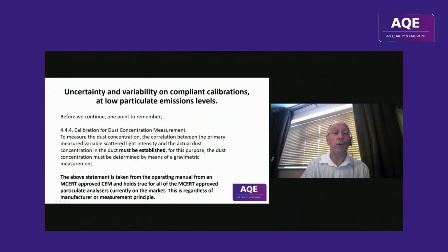Again, it's just confirming the point that no continuous emission monitor for particulate, when it comes out of the box, will give you a concentration of dust straight away. It has to be aligned to a series of standard reference method tests. The above statement is taken from the operating manual from an MCERT approved CEM and holds true for all certified approved particulate analyzers currently on the UK market, again, regardless of manufacturer or measurement principle.